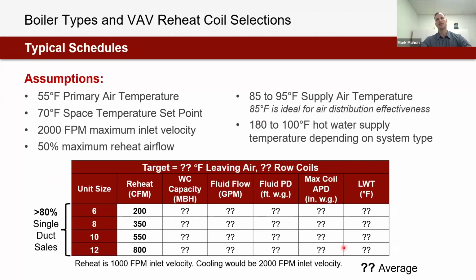So what this little presentation table is, is the ASHRAE Handbook of Fundamentals Classic Single Duct VAV Reheat Schedule. And what we're always going to have is size 6, 8, 10, and 12 terminals. That is representative of at least 80% of the single duct units sold to market from all manufacturers every year. For us this year, it's 83% of the single ducts that we've sold that have been those 4 sizes. And this schedule is set up with 2,000 feet per minute of maximum inlet velocity, which is the ASHRAE Handbook of Fundamentals Classic CFM for a VAV box. It's also the AHRI certified ratings point, essentially where they test our product for pressure drop, sound, all of those great performance characteristics which you populate into schedules.